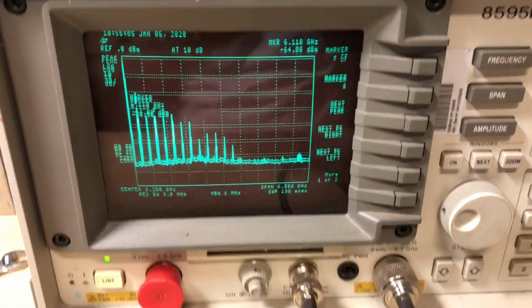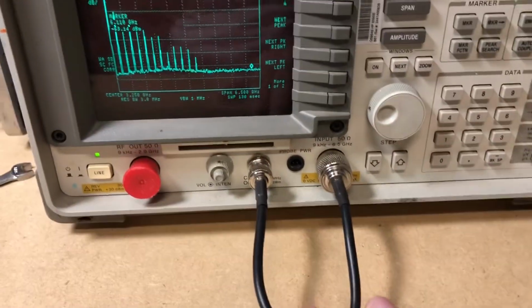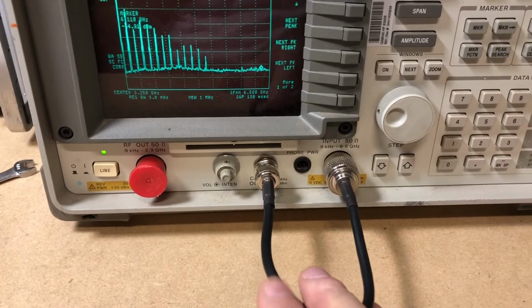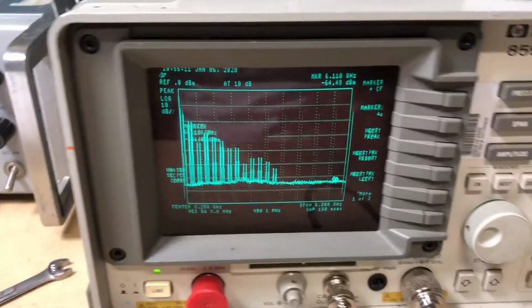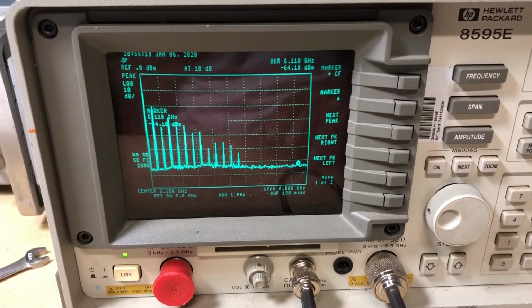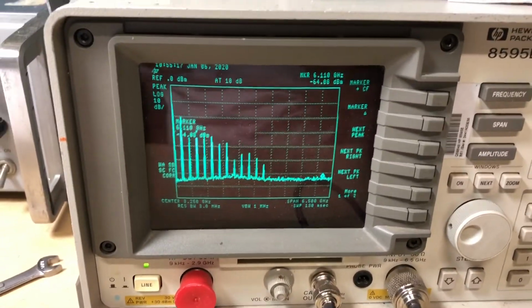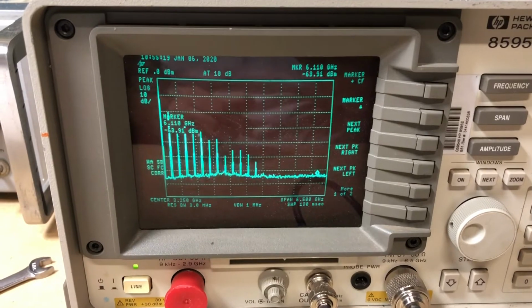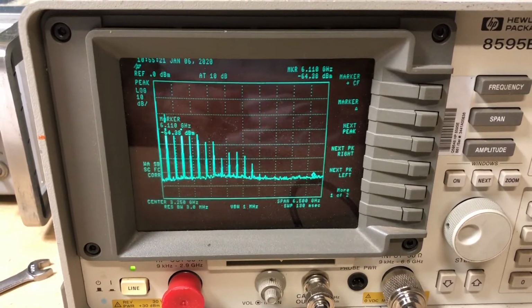Back on the analyzer now, we've got the reference, the cal out signal hooked back into the RF input. And so what we're going to do next is I'm going to go ahead and run the cal frequency and the cal amplitude routines, and we'll see what kind of response we get.